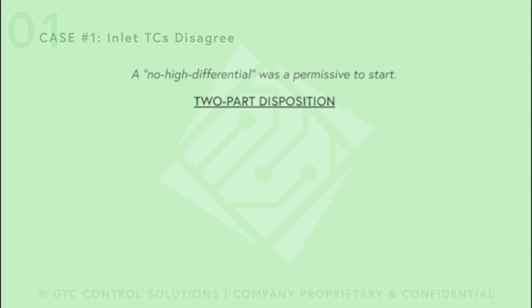First case of the single point of failure. It's about 4 units that have disagreement of the inlet ambient temperature thermocouples located at the inlet filter house. So they were readily accessible, very easy to get to, and the customer complaint was we have a not-ready-to-start condition, and we troubleshot to these ambient temperature thermocouples. There are 3 of them. They are voted thermocouples. But what happened is that we need a no high differential condition to be able to start the unit. So the ready to start depends on a no high differential condition of these 3 thermocouples. So we arrived to a 2-part disposition. But let's first review how we arrived to that 2-part disposition.